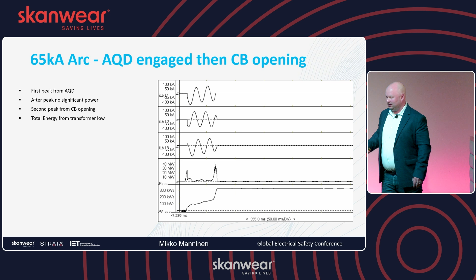And we can compare, I will skip to the last one here. So we can compare it to this one. Left side, same fault with the arc quenching, and same fault without arc quenching. So 5 megawatts instead of 300 kilowatts. So this kind of gives the idea of how arc quenching works. Fault here, quenching here, absorbing everything here.